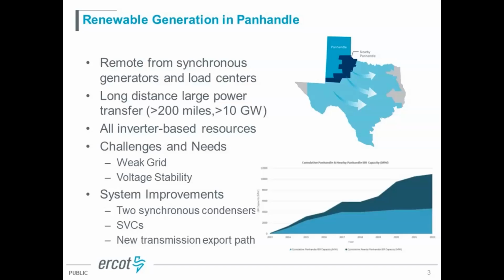When we have close to 30 gigawatts or more concentrated in West Texas, without or with a very limited synchronous machine, the voltage is going to be very sensitive, and the signal may not be robust enough for the inverters to reliably synchronize with the grid.